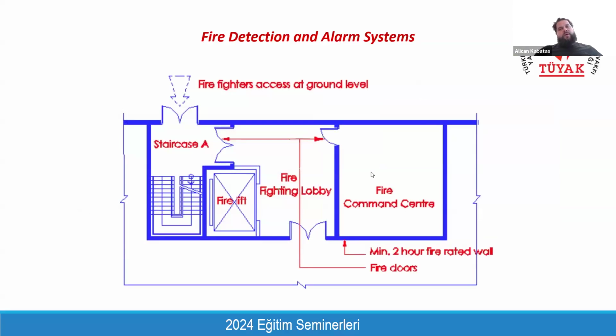It is similar to fire pump room. It should be accessible at any point, at any time, even if the building is having a fire incident. We should reach the fire command center easily and in a safe way. And this room should be 2-hour fire rated so that it will not be affected from fire incident. And it should have a direct access from a staircase so that fire brigade or technical staff of the building can reach easily and safely, even in case of fire.